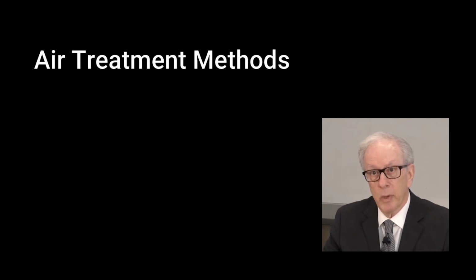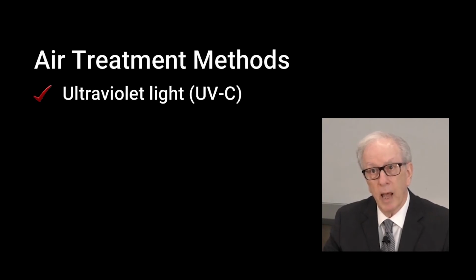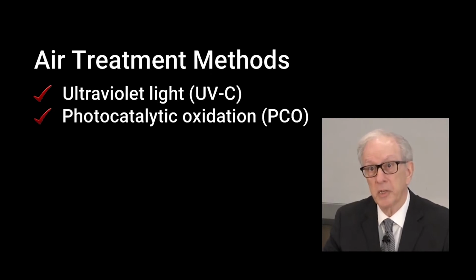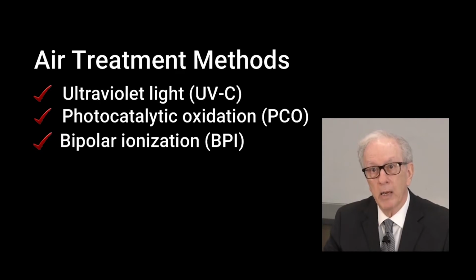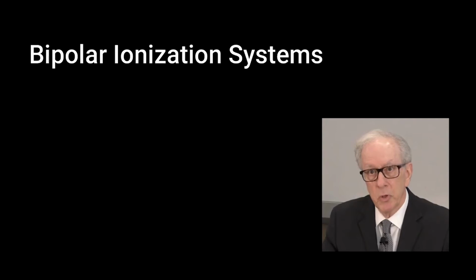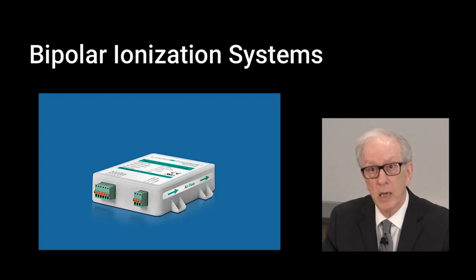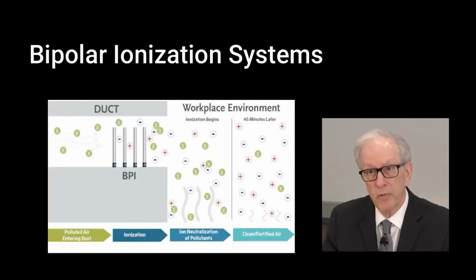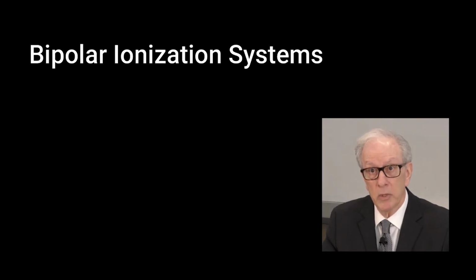Three such methods for doing this include ultraviolet light, or UVC, a process known as photocatalytic oxidation, and bipolar ionization, or simply BPI. BPI systems utilize low wattage glass ionization tubes that are inserted directly into the airstream. Applied alternating current to the electrodes of these tubes creates an ionization field around the tubes, resulting in a supply air stream of positive and negative ions that purify the air in three ways.